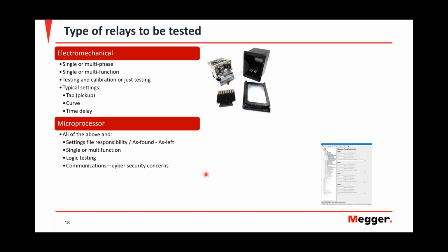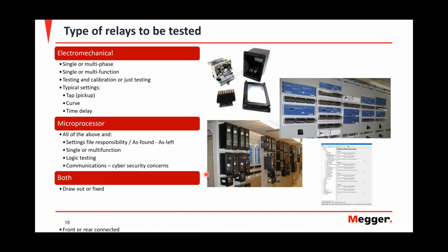Are you testing the communications between the devices, between the routers, the servers? If you're doing that, it's going to require a lot more time. So you have to know what the customer or the end user expectations are of your test, and you also got to know what you're testing as far as how much money you got paid to go out there and do it. And for both, are they draw out or fixed? That might make your life easier, because if they are draw out and you could pull the relay out without disconnecting or shutting down the gear, that makes matters easier.